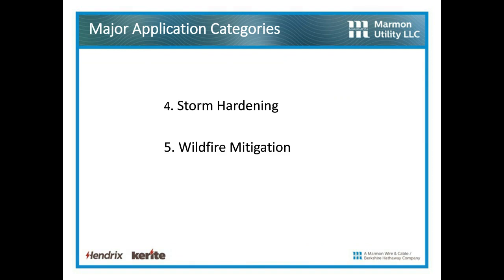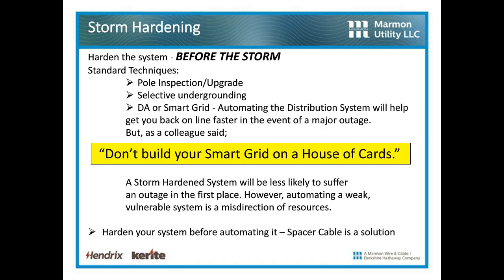Two other categories that have come up: one's called storm hardening, the next is wildfire mitigation. So, storm hardening. It's interesting when you look into it. I know a lot of the big utilities have storm hardening programs, especially after being hit by massive hurricanes. It's important to harden the system before the storm, not after the storm. Be proactive about it. Standard techniques, if you look at the literature: the first one is pole inspection and pole upgrade, then selective undergrounding, put underground cable in places where you think it will do you the best. And the third category is distribution automation or smart grid. So obviously automating the distribution system will help get you back online faster in the event of a major outage.